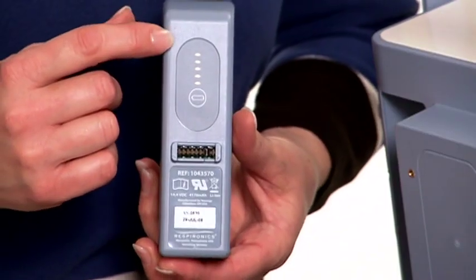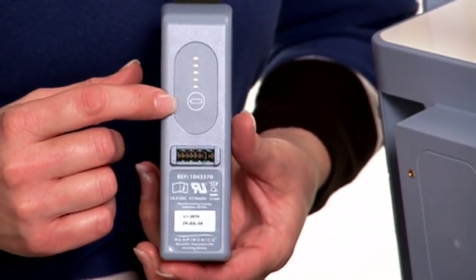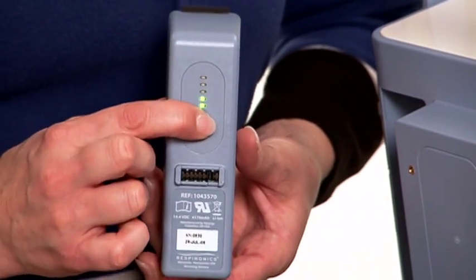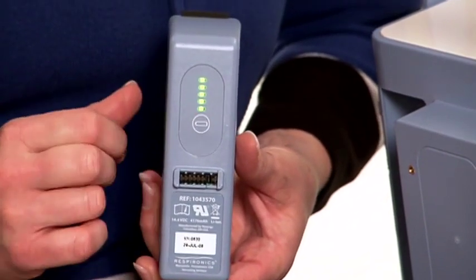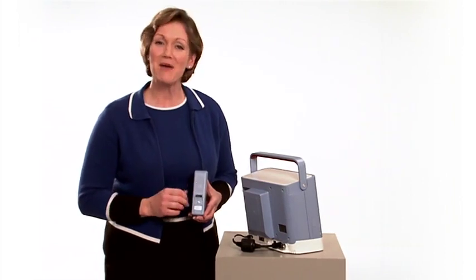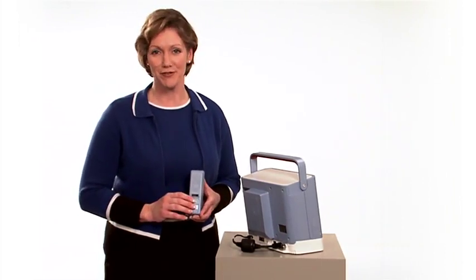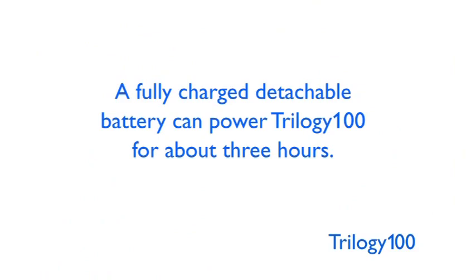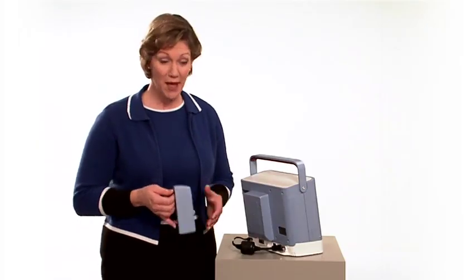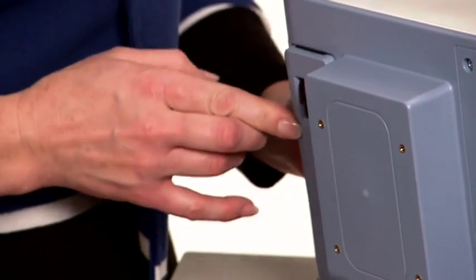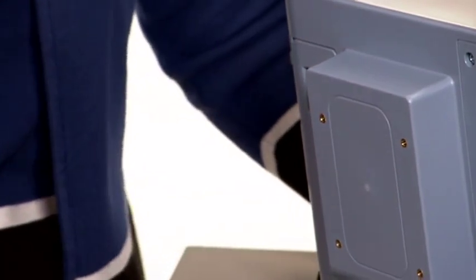Here on the back of the detachable battery, you can see a set of LEDs. Press the button below to see how much charge is left in the battery. When all the LEDs are lit, the battery is 80 to 100% full. Under typical conditions, a new fully charged detachable battery can power Trilogy 100 for about 3 hours. The detachable battery snaps easily back into place on the back of the ventilator.